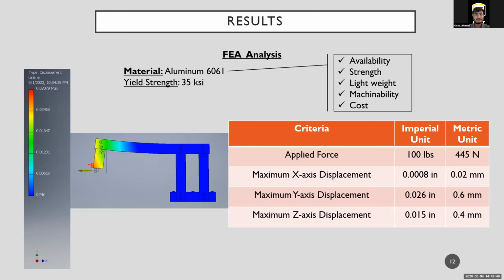So we ran a simulation on our arm, applying the maximum force we can achieve, which is 100 pounds, close to 445 Newtons. The maximum displacement that might occur is in the y-axis, which is 0.6 millimeter, if and only if we get the maximum load on it. We can always expect a lower load or lower displacement on any axis. The value is very small and the effect will be negligible, so we have approved the arm design for the equipment.